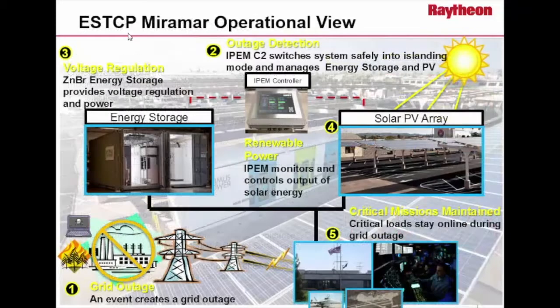Let's go to the next slide. So the operational overview for the islanding scenario is when a grid outage would occur, our IPEM C2—Intelligent Power and Energy Management microgrid controller—would detect that and then manage the energy storage and PV to first disconnect the building from the base grid, then bring the energy storage up in black start, so that it starts providing voltage and frequency, and then bring the solar PV online to synchronize with the battery as if the battery were the grid in this case.